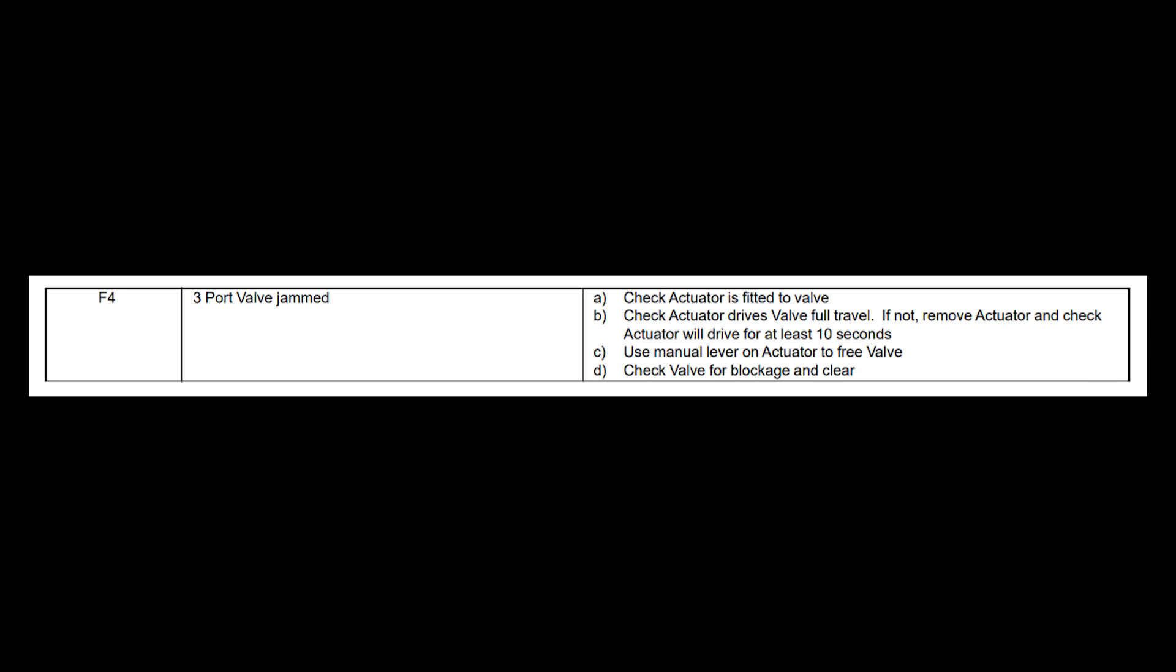In the fault finding documentation for the Honeywell Smart Fit, the F4 fault code means that the three-port valve is jammed.